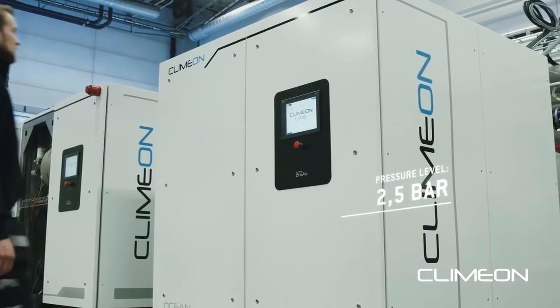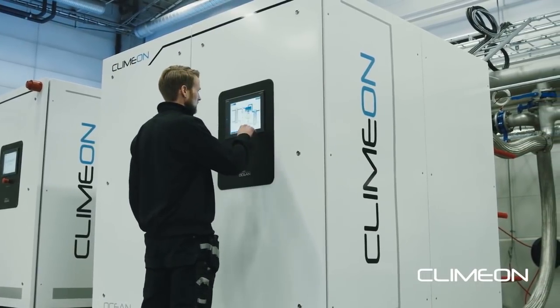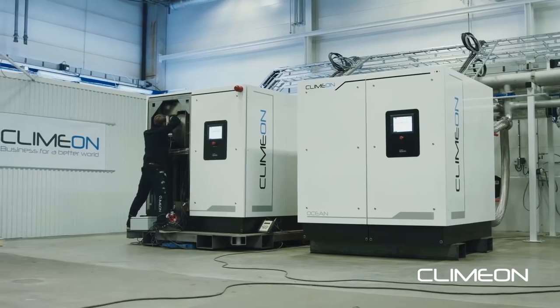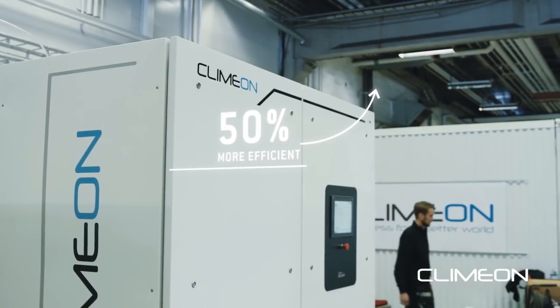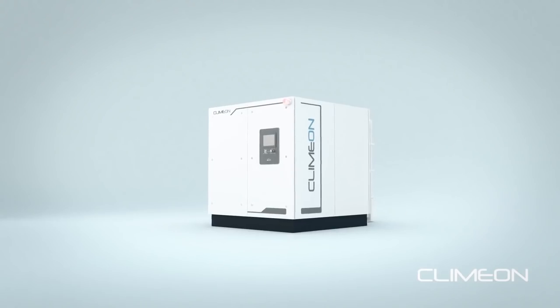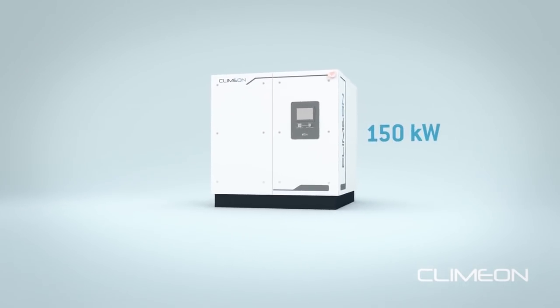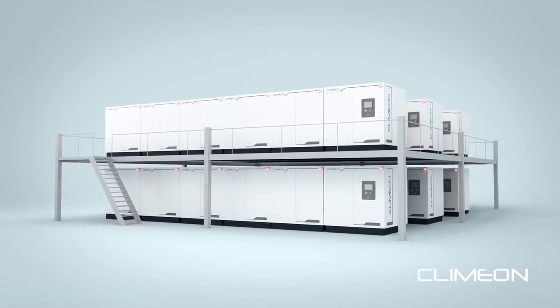The technology operates at low pressure levels compared to traditional heat power solutions, which are both larger in size and less efficient at low temperatures. At these low temperatures, Climeon delivers up to 50 percent higher efficiencies than other solutions on the market. The system's low pressure levels allow a compact and modular design, making it easily scalable from 150 kilowatt modules to 50 megawatt systems for larger installations.